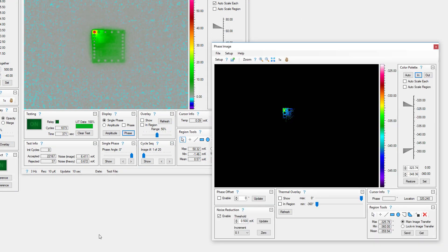Phase images display the phase angle of heating at each point in the image. Phase angle represents the delay between powering a device and the resulting surface heating. When analyzing package devices and stacked die, phase angle is used to estimate the depth of a defect.